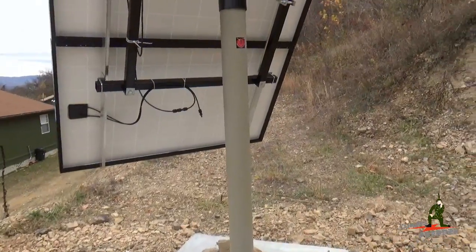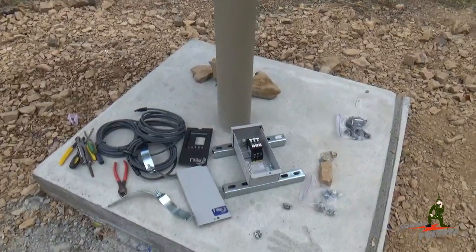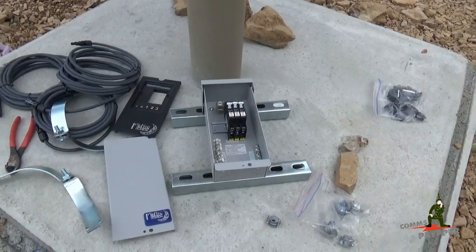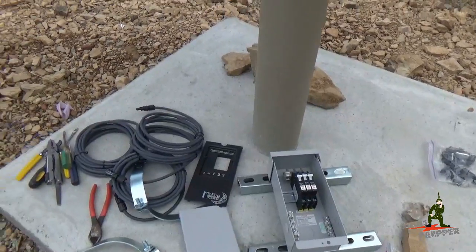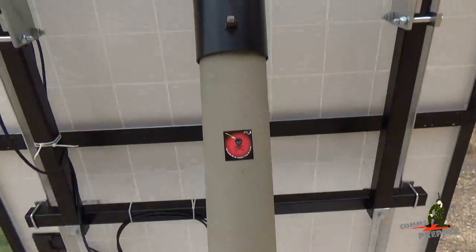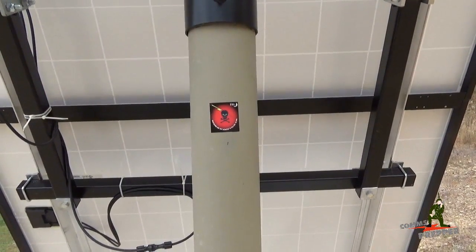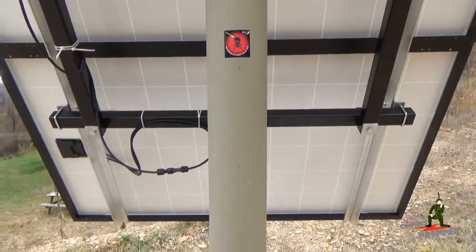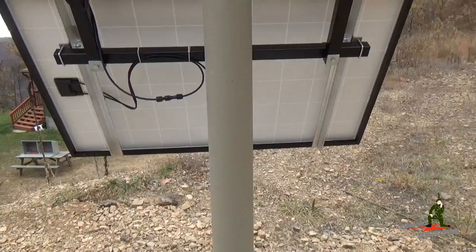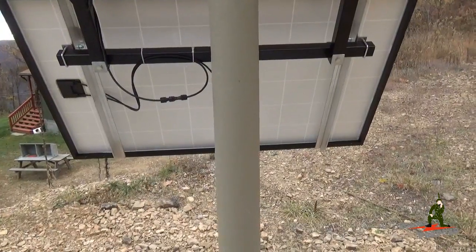Today we're going to mount the combiner box, which is made by Midnite Solar. We have three DC breakers in here, a little bit of uni-strut on the back side, the face plate and some extension cables. The plan is to get this box mounted up here on the 5-inch pipe, get the panels wired into it. We kind of redesigned this a little bit — I have on order a Hoffman box that will sit just below this, and in the Hoffman box I'm going to put the charge controller and the inverter for this system.